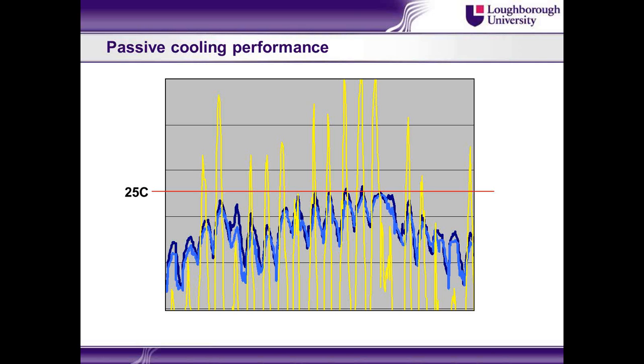I talked about A and B buildings at the beginning, and it's more than just opening windows. If you just open the window, the temperature you get inside is pretty much the temperature you've got outside. So if it's 30 degrees outside, simply opening the window isn't going to deliver you the passive cooling you need. Because we have got a thermal mass in this building and nighttime ventilation, and we're controlling the openings so that we don't flood the building too quickly with outside air when it gets really warm, we're able to reduce that peak temperature.